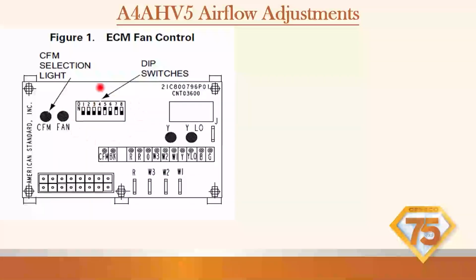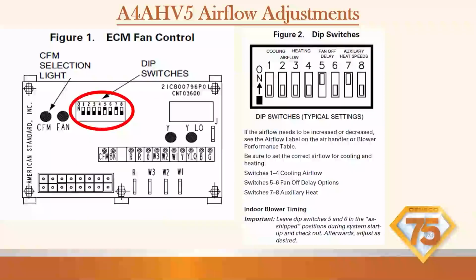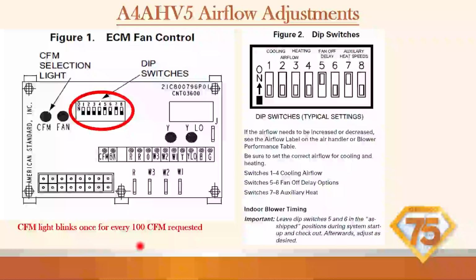Again, this one has a separate dip switch fan bank, CFM selection light. So when you are actually running the indoor fan, this will blink per how many CFM you have running through it. So it is a nice confirmation for CFM. One through 4 are airflow adjustments, fan off delay, and auxiliary heat speeds. Oh, there you go. CFM light blinks once for every 100 CFM requested. So if you're running at 1200 CFM, it'll blink 12 times.